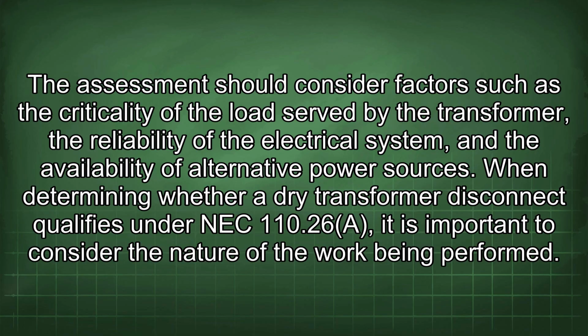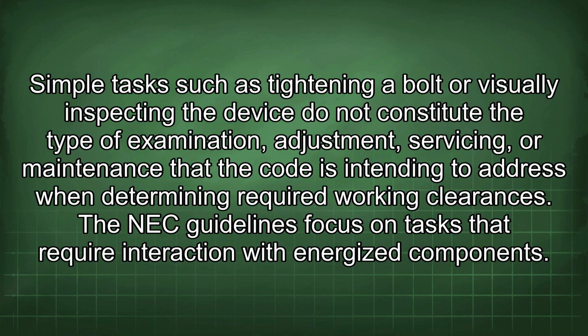When determining whether a dry transformer disconnect qualifies under NEC 110.26(A), it is important to consider the nature of the work being performed. Simple tasks such as tightening a bolt or visually inspecting the device do not constitute the type of examination, adjustment, servicing, or maintenance that the code is intending to address when determining required working clearances. The NEC guidelines focus on tasks that require interaction with energized components.